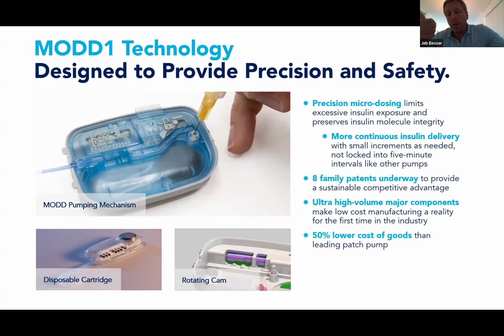One, because we're reusing the electronics, and two, because we're reusing electronics from other industries, and because we're just frankly reusing the electronics, period. You think about how precise you have to be to pump insulin. You have to be precise to smaller than a 200th of a drop with about 5% accuracy every time. That's a lot of know-how and our competitors get there by machining. We get there by pumping more frequently and sensing how much we've moved and using a very different method. And that is a major, major proprietary advantage.